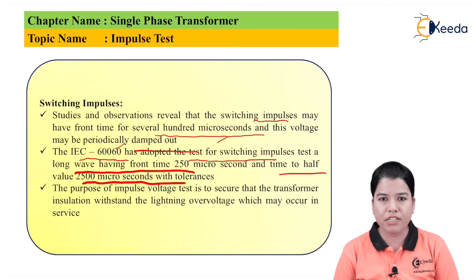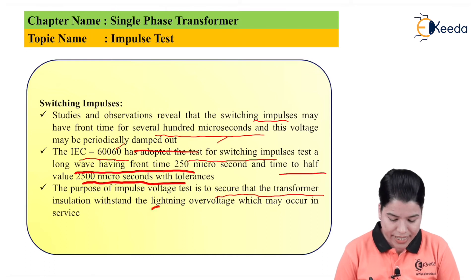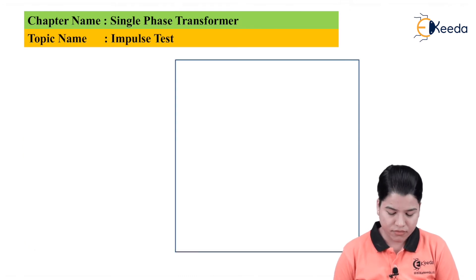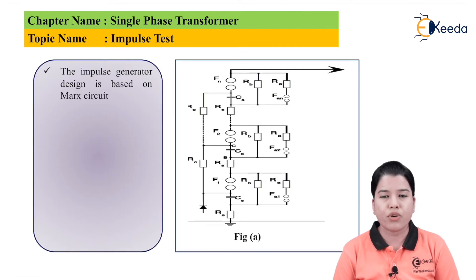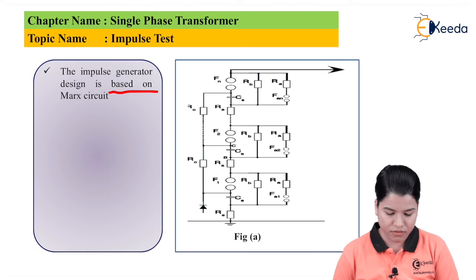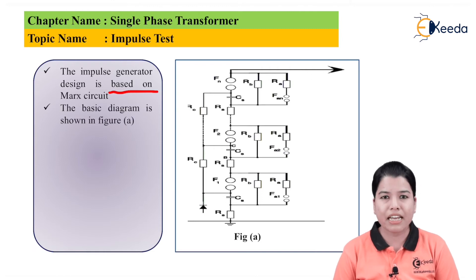The purpose of the impulse voltage test is to ensure that the transformer insulation will withstand the lightning overvoltage which may occur in service. When the transformer is connected in the transmission line, a certain amount of lightning overvoltage may always occur, and the main aim of this test is to check whether the transformer insulation can withstand these high voltages. In order to create the high value of this voltage, an impulse generator is used. The impulse generator is basically based on the Marx circuit, as shown in Figure A.